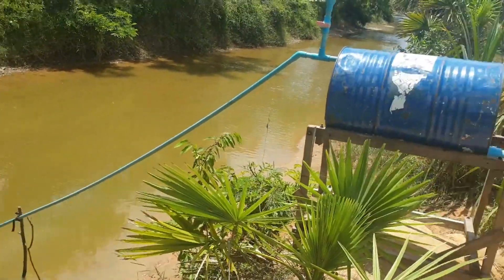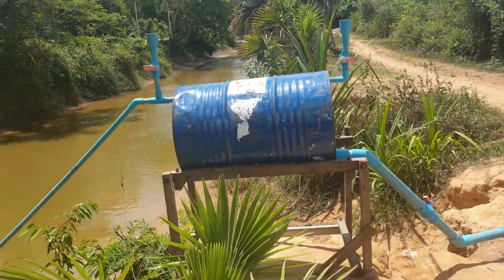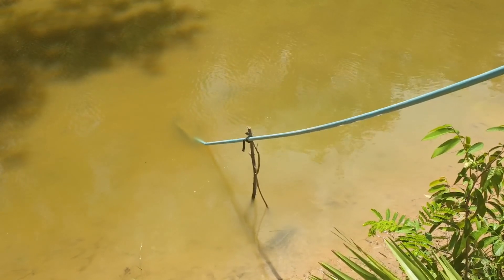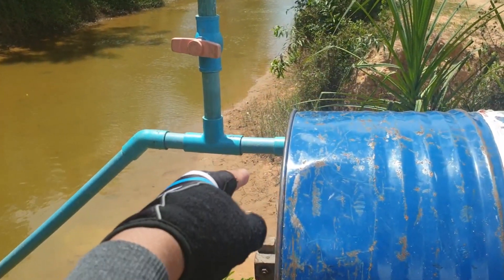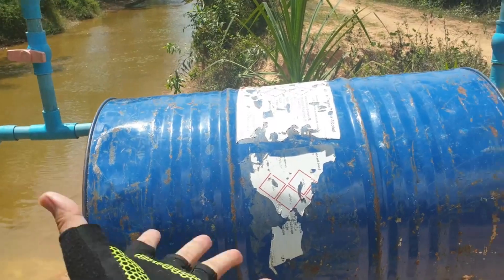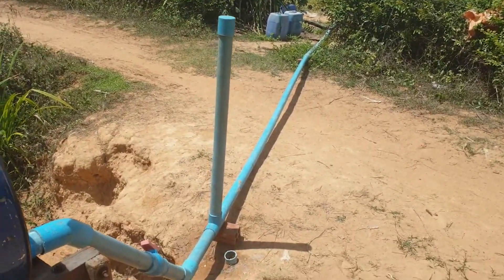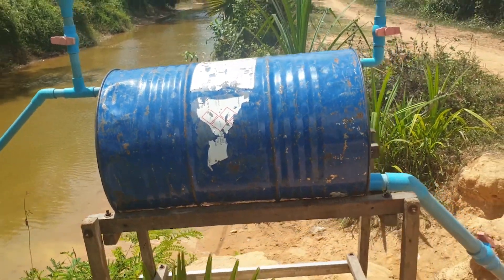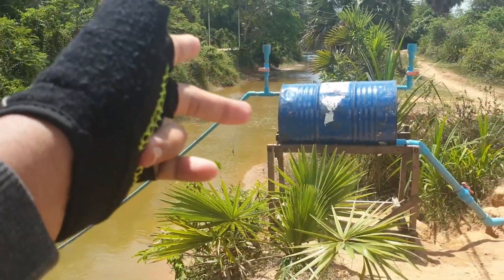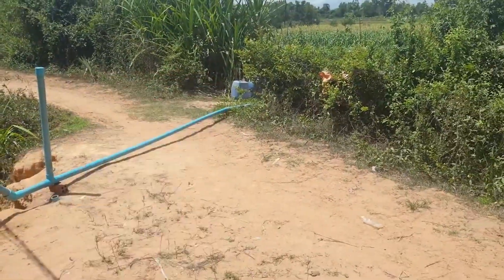This is how the drum works. As you can see over here, this is the intake water pipe from the river. They have the foot check valves at the intake water part. The pipe is filled with water during installation. When the output is opened, the water makes the drum compress — the drum needs air replacement inside. The water that stays inside the intake water pipe drops down into the drum to replace the air when we open the output water pipe.